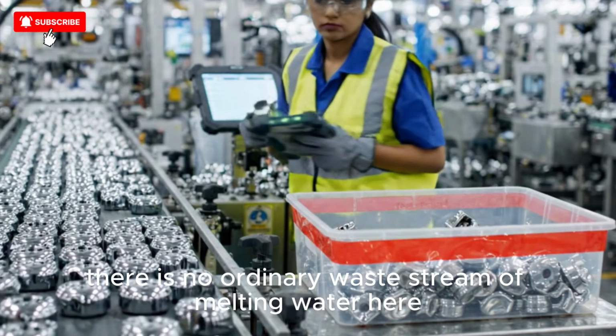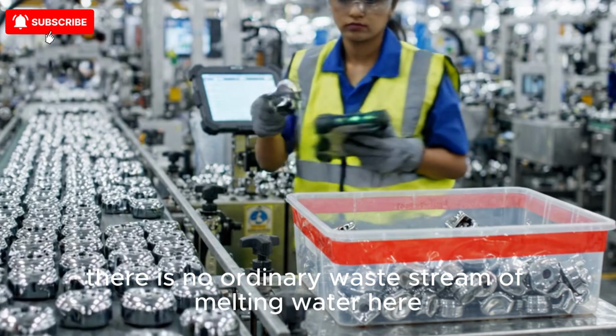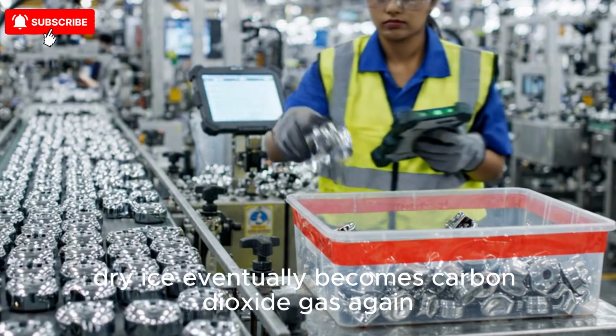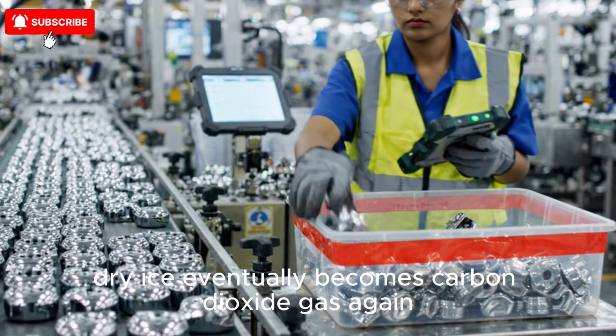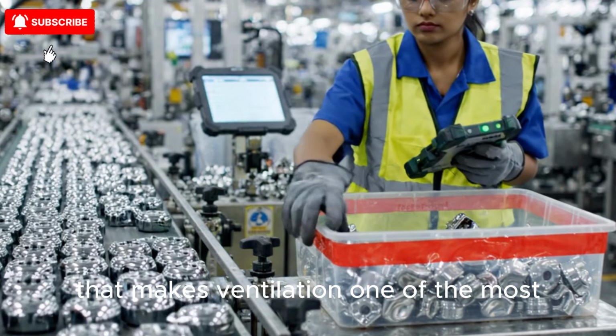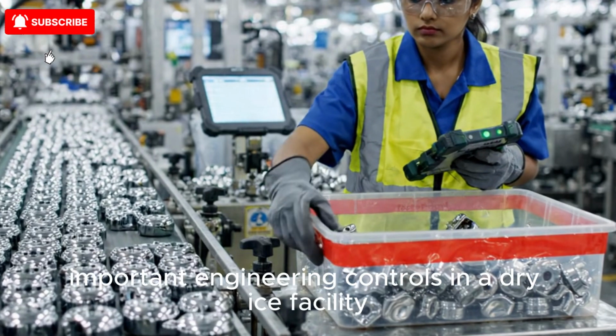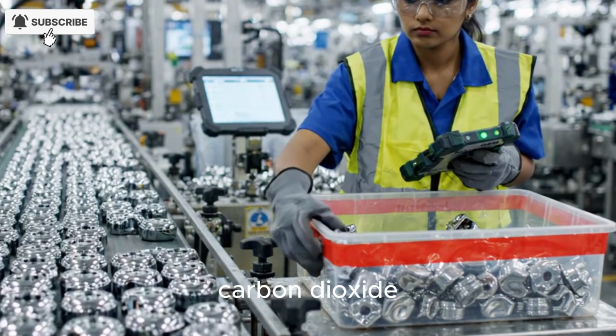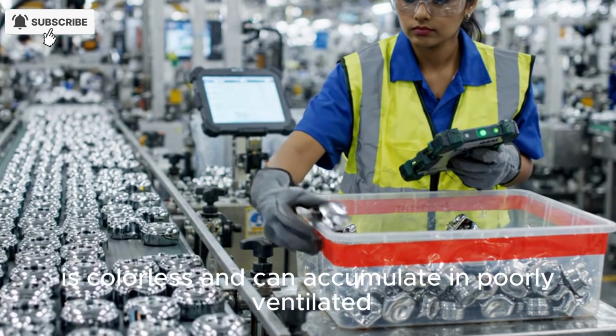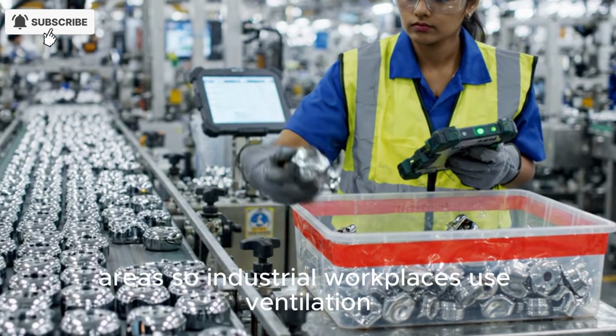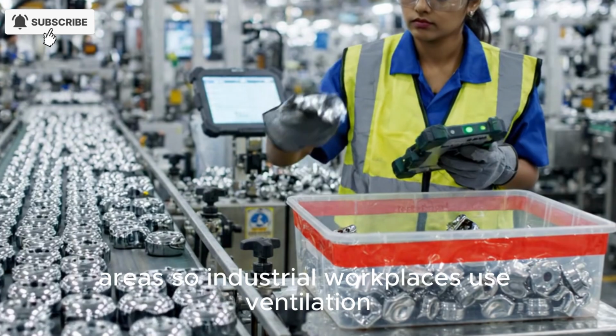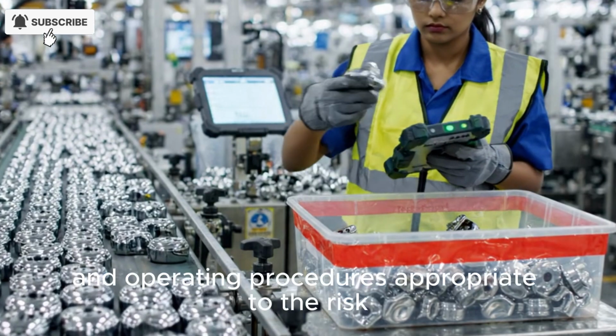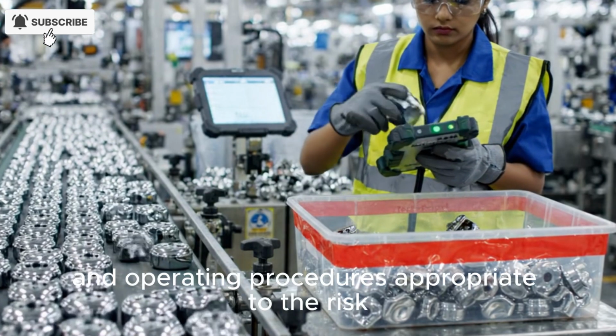There is no ordinary waste stream of melting water here. Dry ice eventually becomes carbon dioxide gas again. That makes ventilation one of the most important engineering controls in a dry ice facility. Carbon dioxide is colorless and can accumulate in poorly ventilated areas, so industrial workplaces use ventilation, gas detection, and operating procedures appropriate to the risk.